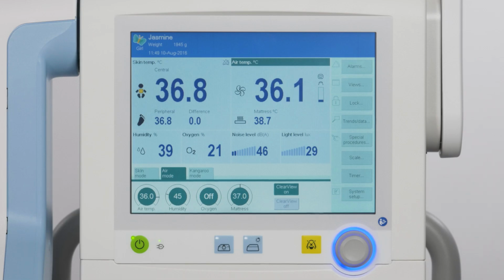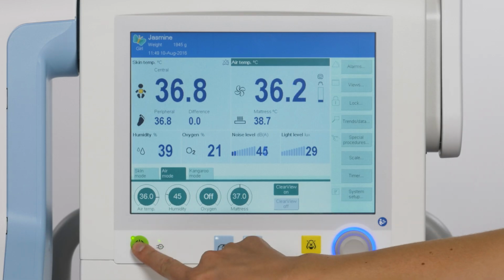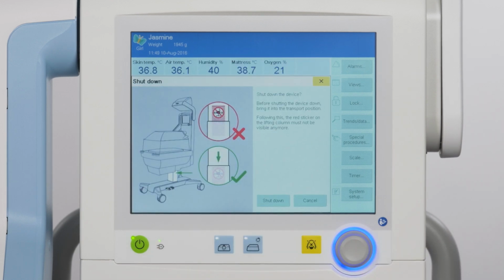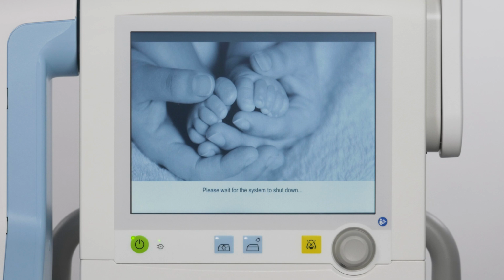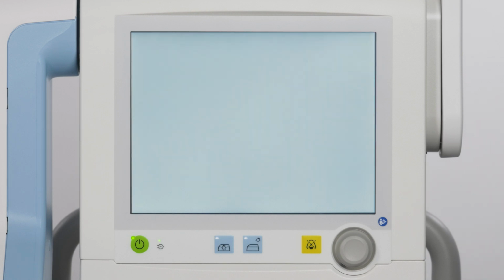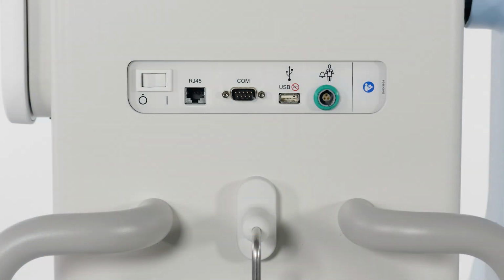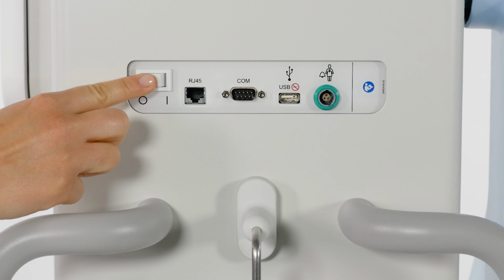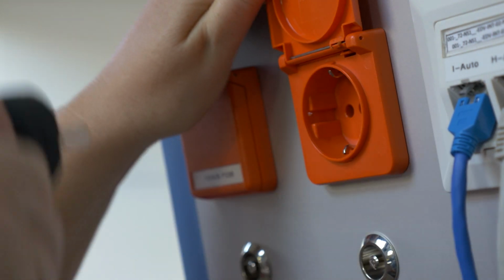Switch off the device by pressing the Start Standby key. Next, touch the Shutdown button and confirm. Finally, turn off the main switch on the main column and disconnect the mains power plug.